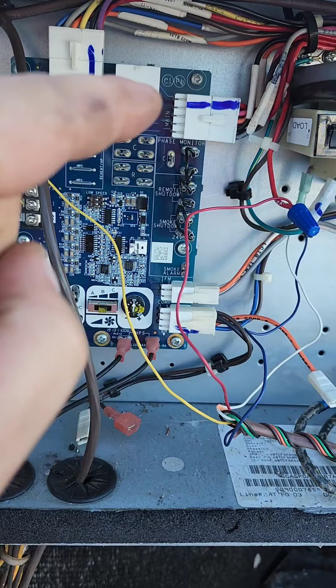That's your economizer, low pressure switches, everything - same thing, no voltage coming into it. Everything else works, smoke sensors, everything's tied in, so it's a bad board.